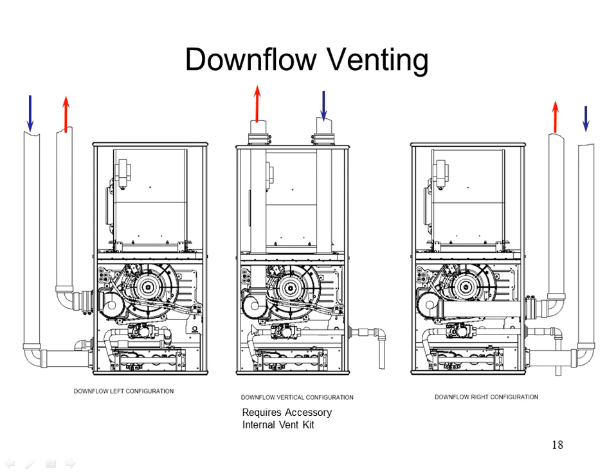So the elbow would be pointing downward, which obviously would not be very good for our combustion gas. So I need to rotate him to the left and vent out the left side, or rotate him to the right and vent out the right side. I could, if I really had to, rotate that elbow 180 degrees and then cut through the blower housing to vent him out what is now the top of the furnace.